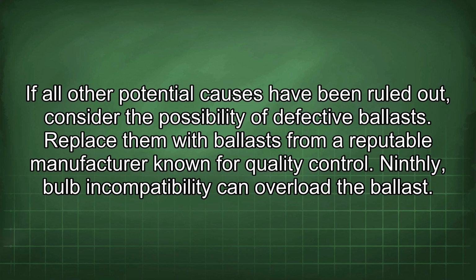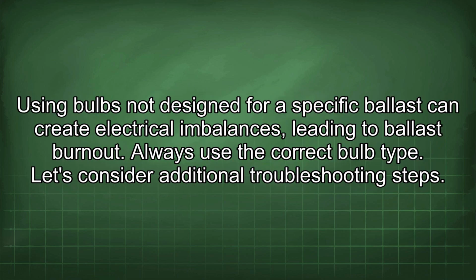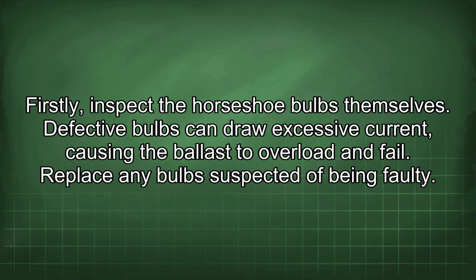Ninthly, bulb incompatibility can overload the ballast. Using bulbs not designed for a specific ballast can create electrical imbalances, leading to ballast burnout. Always use the correct bulb type. Let's consider additional troubleshooting steps. Firstly, inspect the horseshoe bulbs themselves. Defective bulbs can draw excessive current, causing the ballast to overload and fail. Replace any bulbs suspected of being faulty.